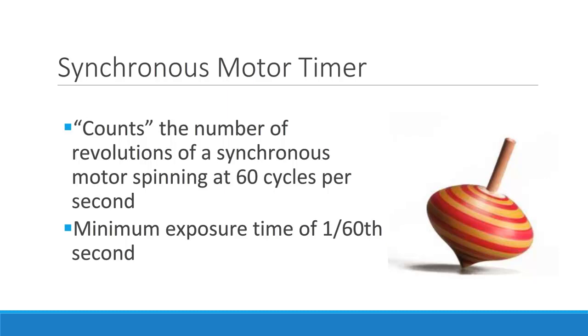The synchronous motor timer counts the number of revolutions of a synchronous motor spinning at 60 cycles per second. Once the timer counts the correct number of revolutions, the manually set exposure is terminated. This type of timer is able to produce a minimum exposure time of 1/60th of a second, as it is limited by the number of revolutions per second.